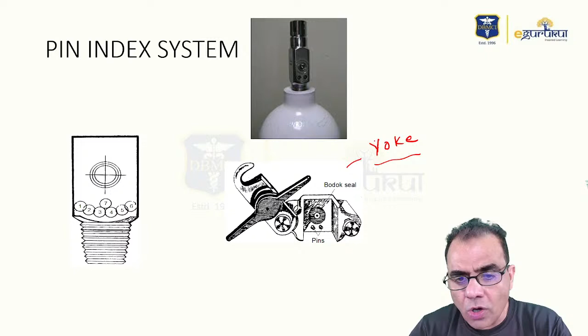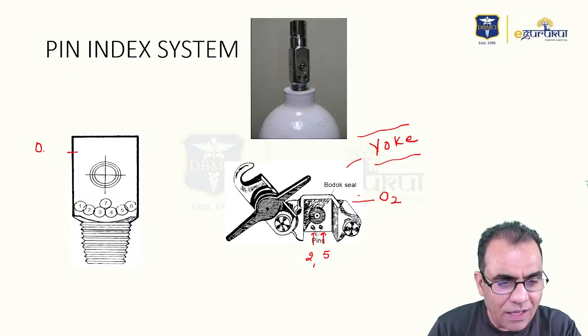So this is the portion where cylinders get fitted on the anesthesia machine, and this portion is called the yoke. So the yoke is that part of the anesthesia machine where cylinders get fitted. Now say, for example, this is a yoke for oxygen. You can see these two pins. So what pin positions are you expecting here? That is 2 and 5. And say this is an oxygen cylinder. What holes are you expecting? That is 2 and 5. Can you see these two holes? The position of these holes is 2 and 5, and the pin positions at the yoke are 2, 5. So only an oxygen cylinder can fit here.